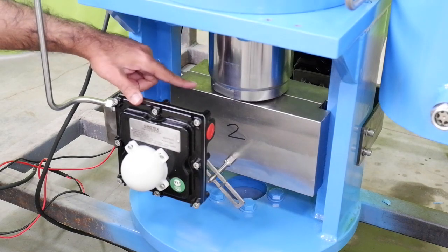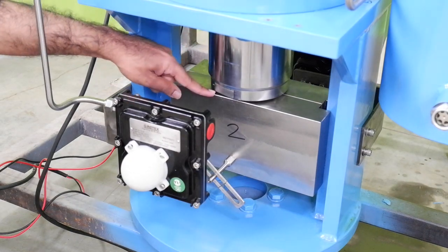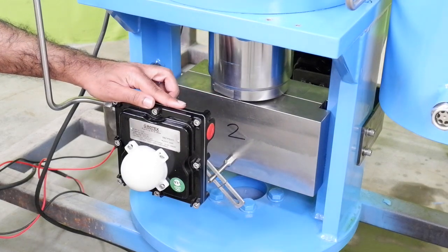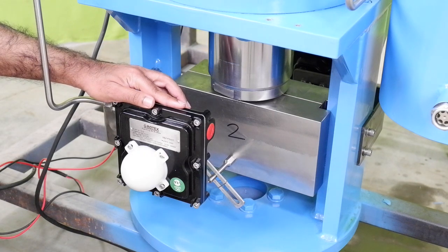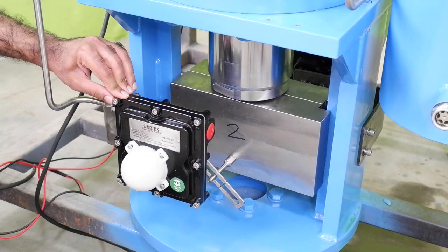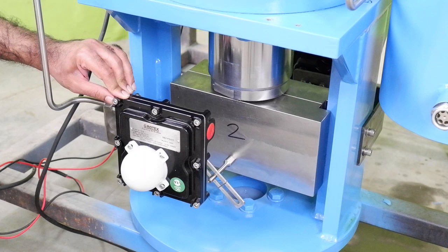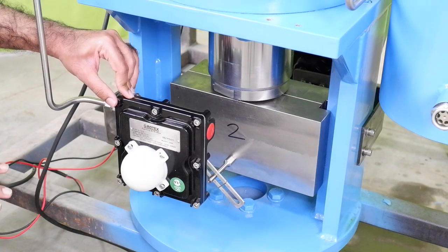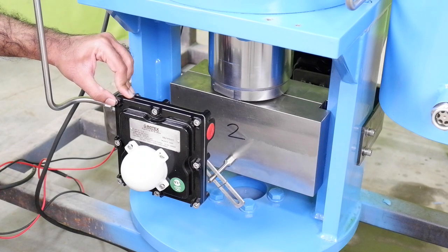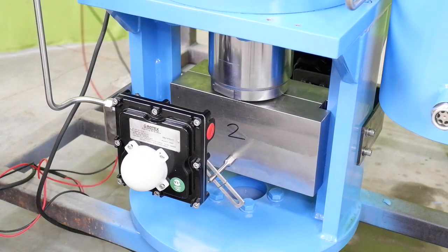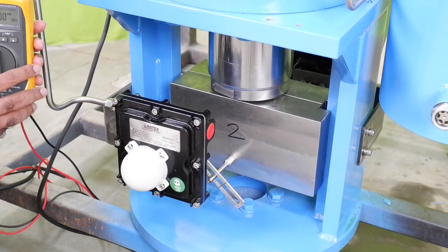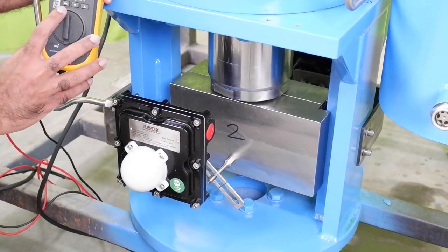Here the cylinder is connected to a split coupler. The split coupler reduces the play between the stem of the globe valve and the cylinder. The transmitter is connected directly to the coupler along with the linkage, which improves the accuracy of the system. Now we will see how the cylinder opens and closes with respect to the set point signal.